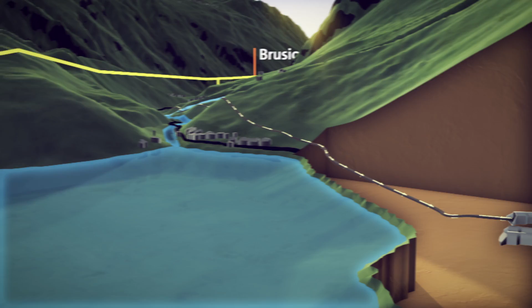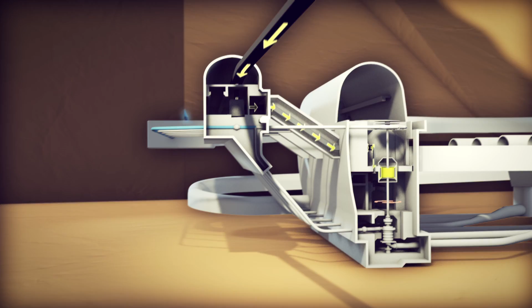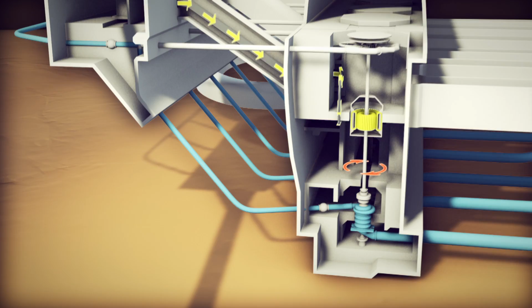It's the other way around when Lagobianco's in pump mode. Here the plant will take electricity from the grid. The generator now acts as a motor, driving the pumps via a shaft. That's how the water is brought from Lago di Poschiavo back up to Lagobianco. There it'll be ready to generate electricity again when required.